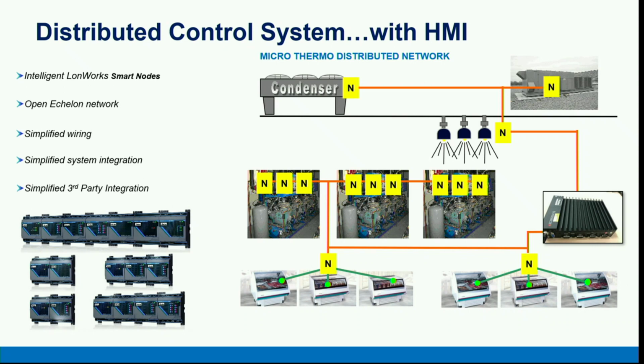And it's an industrial computer because it's military spec, with a redundant hard drive, and all of the horsepower of the Windows platform that's on board is focused to run Microthermo only. No bloatware for social media, for gaming, none of that stuff is on there. That is the HMI, the human-machine interface. That allows you, the human, to get inside of the network and see what's going on and have access virtually to the physical hardware in case you have to troubleshoot, change a set point or whatnot.